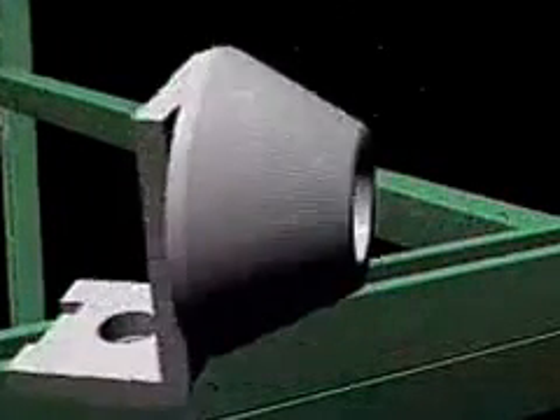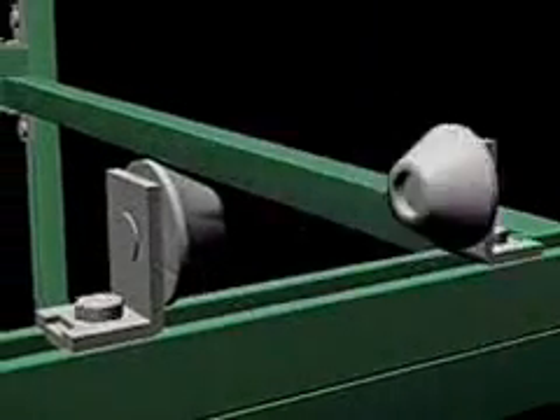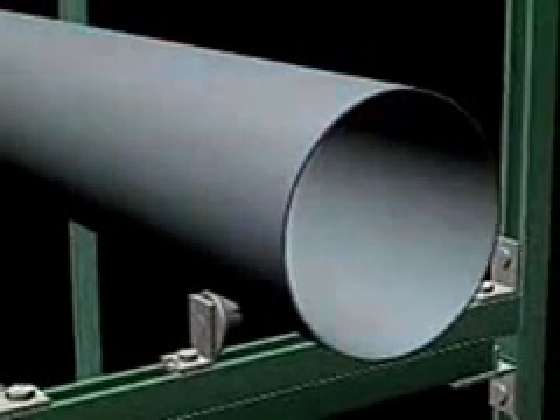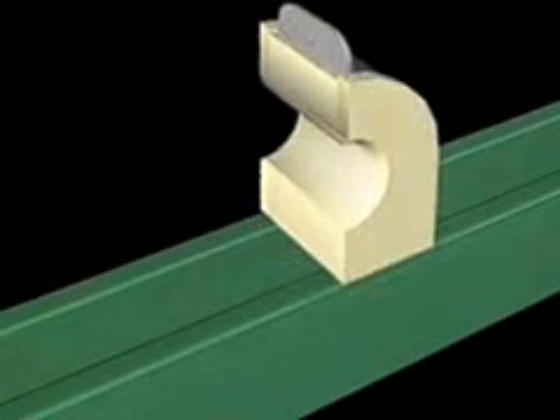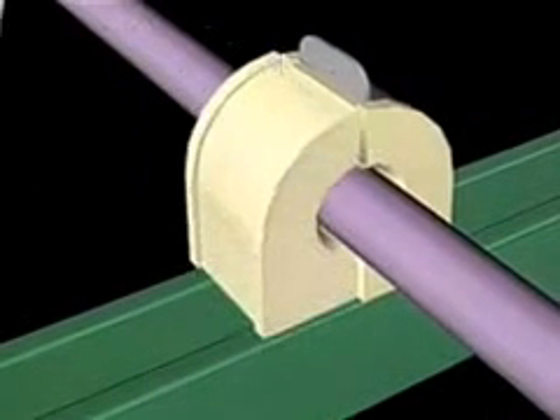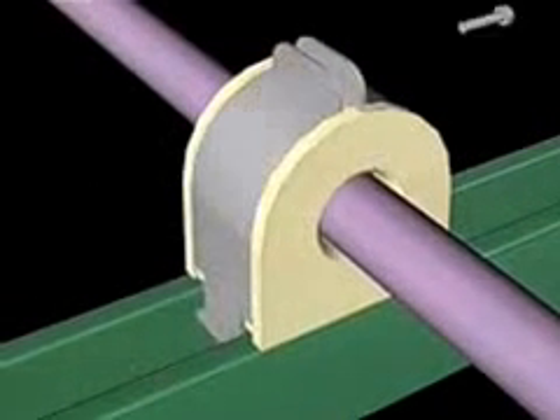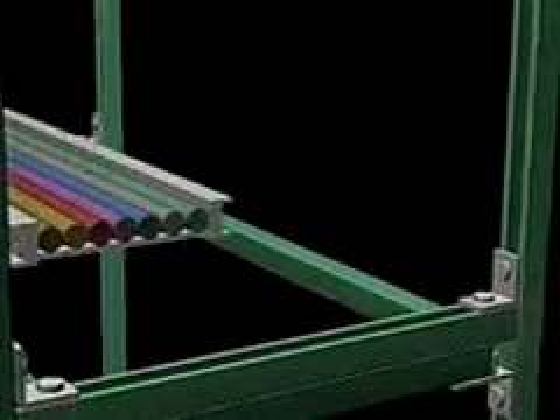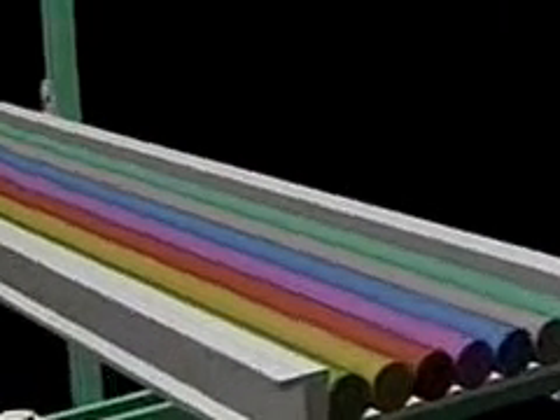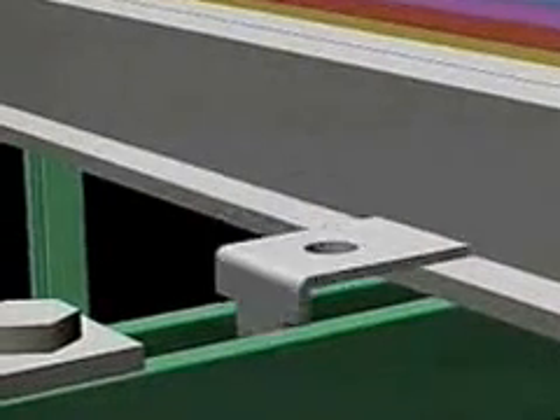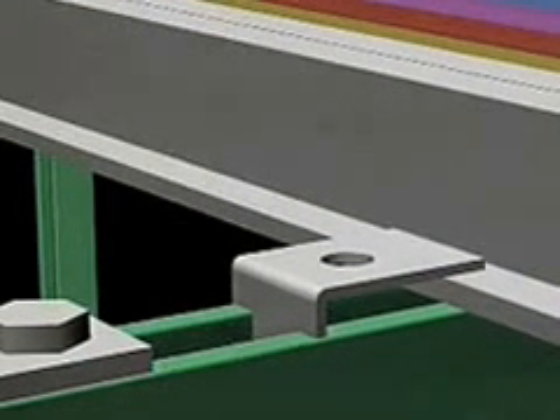Pipe rollers can be used for conditions caused by pipe expansion or contraction. They are positioned on the channel and quickly secured with a nut and bolt. To support individual cables, simply position the cable on the channel support and clamp with porcelain insulated clamps. To support multiple power and signal cables, position cable tray on the horizontal member of the stanchion and clamp with a suitable clamping device. It's that easy and should take only about an hour to assemble and install all of these Unistrut components.